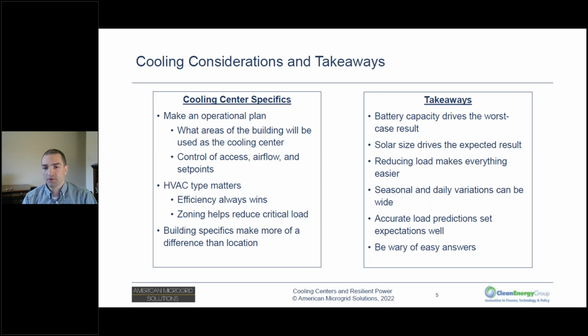And then the last thing: building specifics make a huge difference. What really matters is the efficiency of your HVAC, as we already talked about, how secure or well sealed the envelope of your building is. If you have a lot of air infiltration, that's a lot more volume you need to condition than you otherwise would. And how many windows you have in the part of the building you're using, because solar insolation in the summer is a big driver of your cooling load. So those things matter a lot more than where you are in the country, which is why it takes an analysis of your particular building to figure out the right answer.